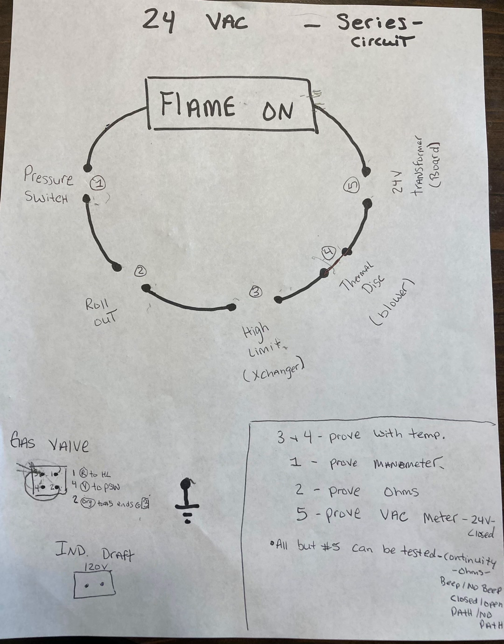If I don't have voltage, there is no 120 volts. Well, then there's no reason the motor should be on anyways, right? Even though we're calling for heat, it's not getting the voltage. So our problem's before then, which is typically going to be our control board area, whatever's sending the signal for the induced draft motor voltage to be present. That's going to be the next series of videos. We're going to be moving into the motor side of the house and how to test these motors and these control boards to see is the signal even going there, and how to take that into further depth.